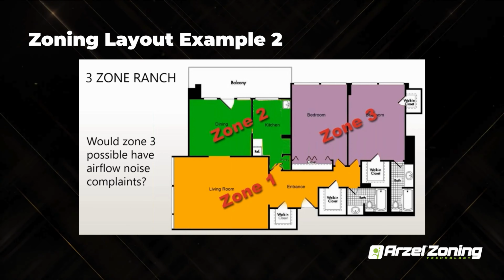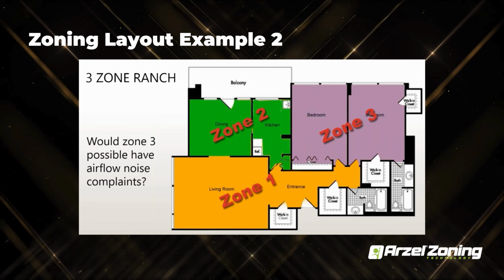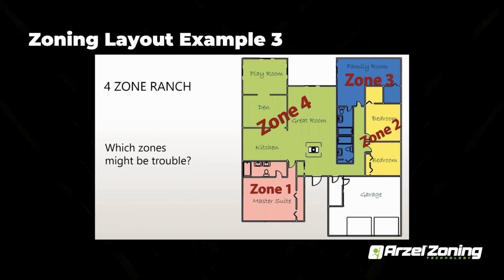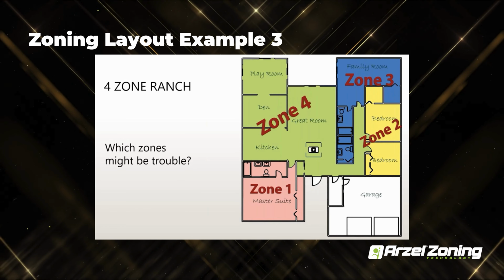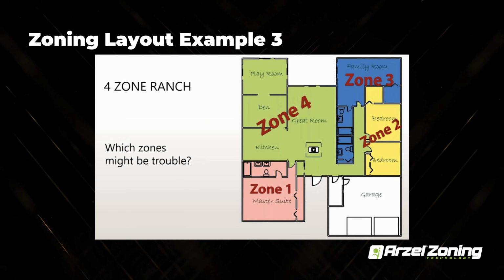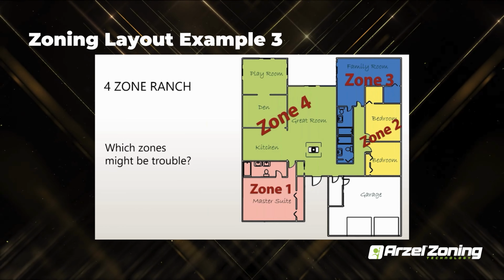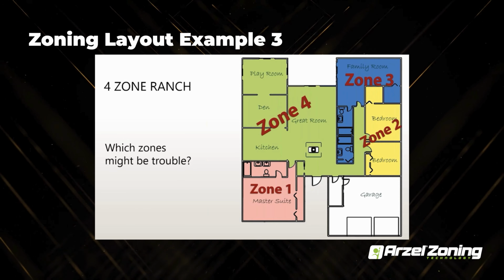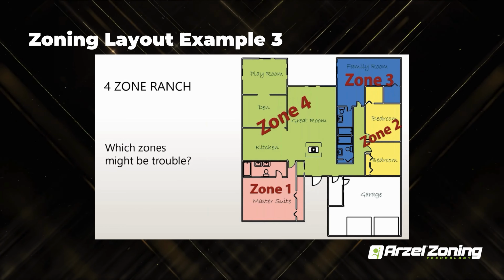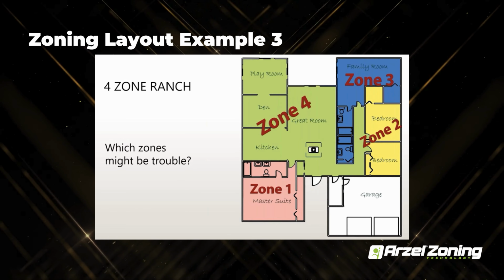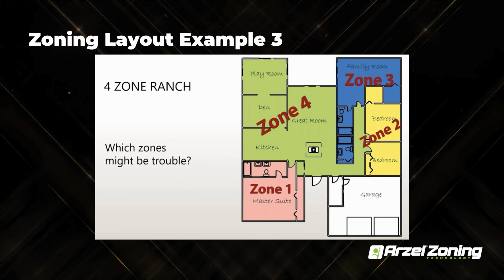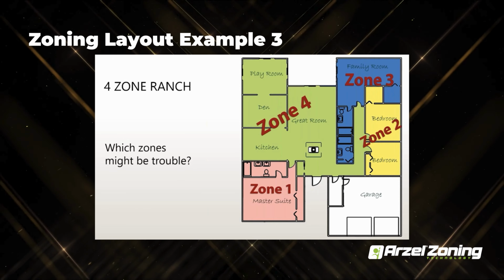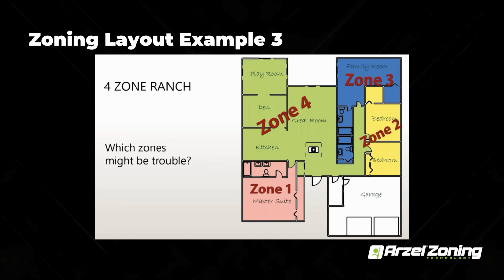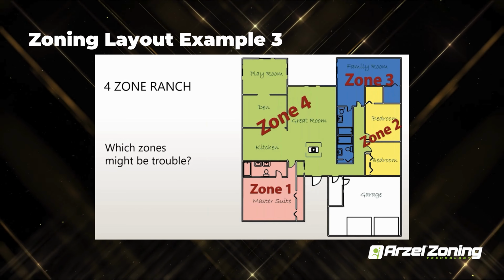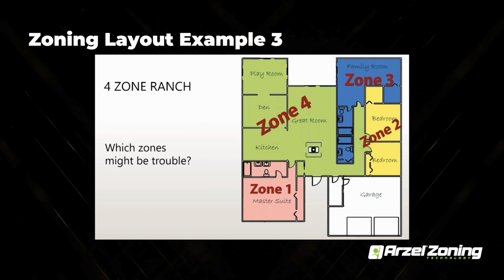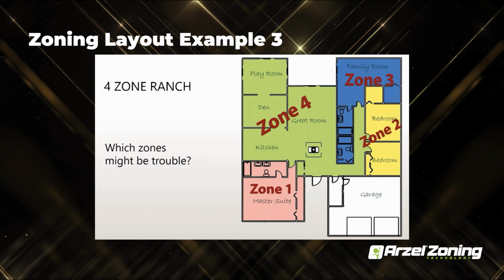So there's a lot of things to consider when you're taking a look at a home. Typically, residentially, you're not going to go over 4 zones, at least we don't like to see it go over 4. There are going to be exceptions on the really big homes, but for your typical residential, 4 zones or under is where we would strive for you to be. That way you're not getting those minimum zones, those micro zones, and having issues with your equipment and overall non-comfort for the customer. So when you're looking at a house like this, with a small master suite and a family room, you'd be almost better off doing slaves, or at least, I would not do this kind of job unless you have 2-stage equipment, and then you utilize that HeatPumPro zone weighting feature.